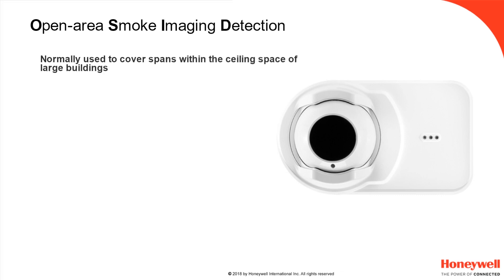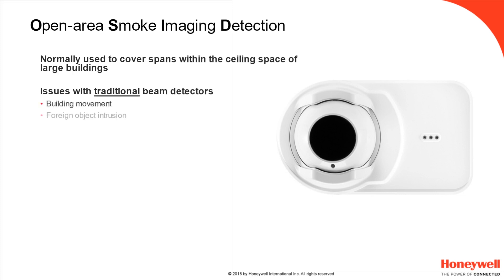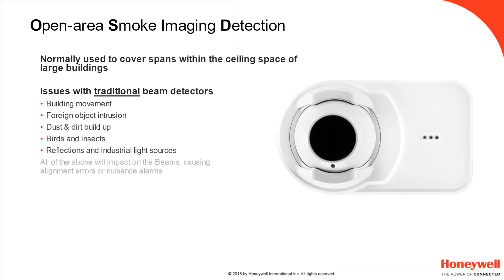Beam detection is normally used to cover large open spans within the ceiling space of buildings. Traditional beam detectors with a single photo receiver are typically susceptible to well-known issues. These range from building movement, foreign object intrusion, dust and dirt build-up, birds and insects, and reflections and industrial light sources.